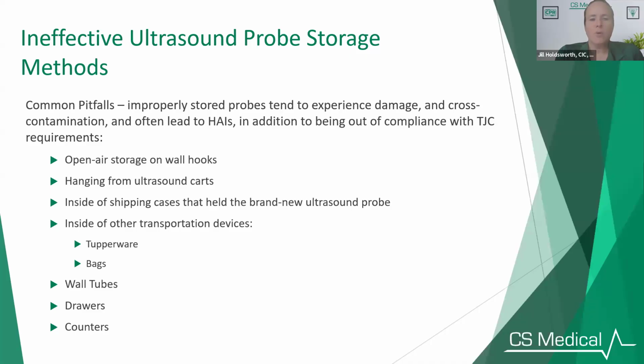So we know that inappropriate ultrasound probe storage will be listed in some of these guidelines as well. You don't want to use open air storage or wall hooks, or hanging on ultrasound carts, which I unfortunately see all the time rolling through these departments. You never want to store it inside the shipping container that it came in. That's a very spongy, porous material, and that is just a breeding ground for all sorts of bacteria. Never in those Tupperware containers or any type of bag. Wall tubes, we see that unfortunately very often, and definitely not on drawers or counters. Next slide.